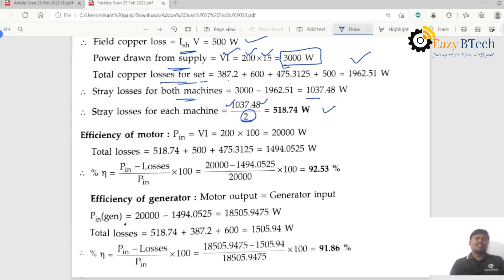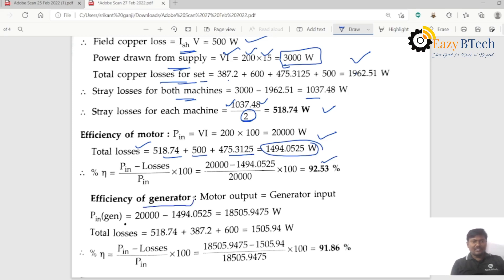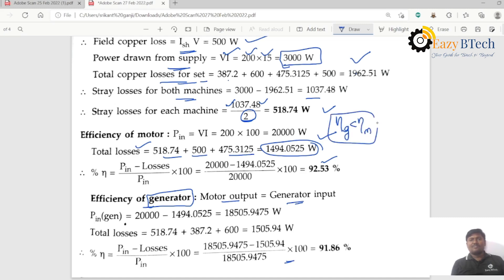Total copper losses for the set are calculated. Stray losses for each machine is 1037.48 divided by 2 equals 518.74 watts. Total motor losses: 518.74 plus 500 plus 475.3125. Input minus total losses divided by input into 100 gives motor efficiency of 92.53%. The efficiency of the generator is less than the efficiency of the motor.